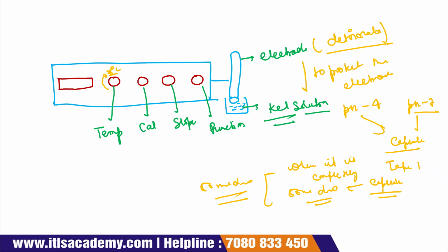So we set it. Then we remove the electrode, as shown in the previous slide. We take that electrode, wash it with distilled water, then dry it, then dip it into the pH 7. After dipping it into the pH 7, you have to move the function key from standby to pH. Here some values are showing.